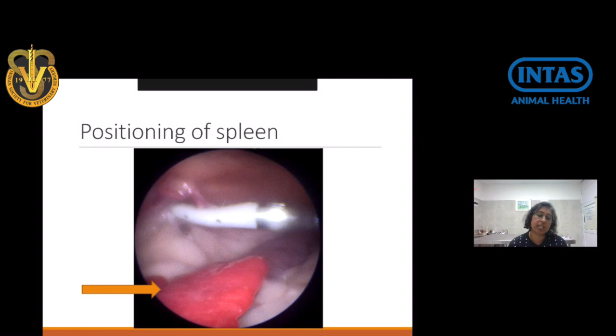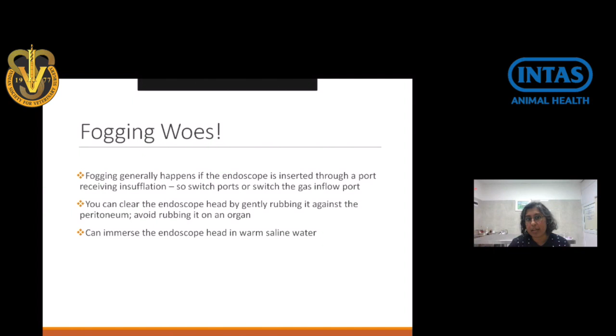Fogging woes. Now, fogging generally happens if the endoscope is inserted through a port that receives insufflation. So it's always better to switch ports, like you switch your endoscope onto the port which does not have the gas inflow. Otherwise, if there is no other option for the time being, you can just switch off the CO2 gas inflow itself. You can also clear the endoscope head by gently rubbing it against the peritoneum, but avoid rubbing it on an organ, again for the same reason that you could injure. You can also immerse the endoscope head in warm saline water if this keeps happening.